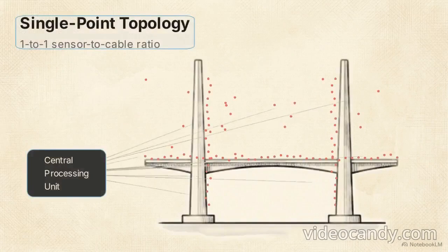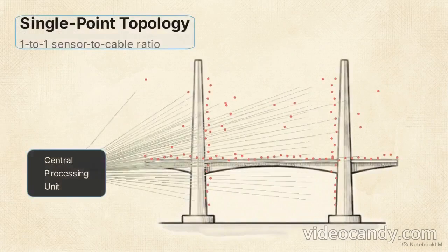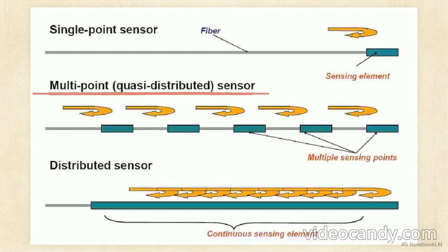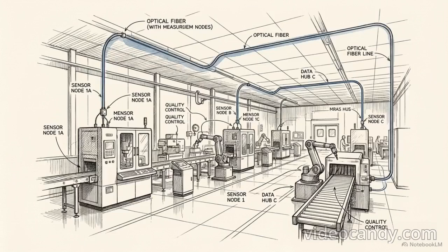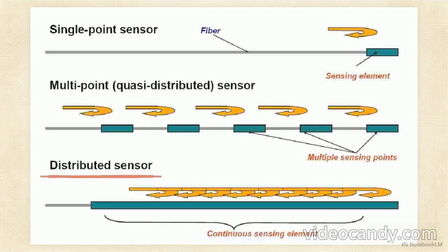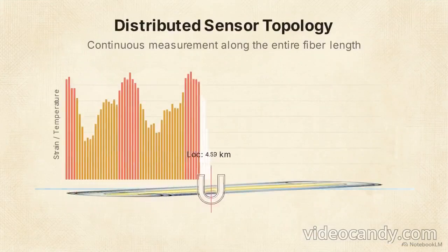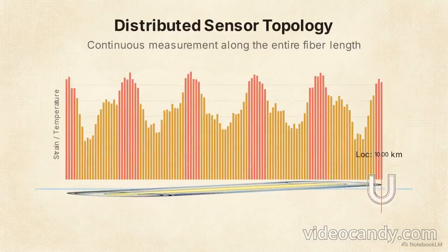The most basic architecture is the single-point sensor. It is restricted to taking a reading at one discrete terminal location at the far end of the line. Monitoring large-scale infrastructure with single-point sensors requires a massive, complex volume of individual cables terminating at exact locations. This logistical constraint necessitates the multipoint or quasi-distributed sensor. This setup multiplexes a finite number of discrete sensing locations along a single continuous fiber path. This drastically reduces wiring complexity compared to traditional electronics, allowing one optical line to service multiple distinct read zones across a facility. The final topological category to explore is the intrinsic distributed sensor.